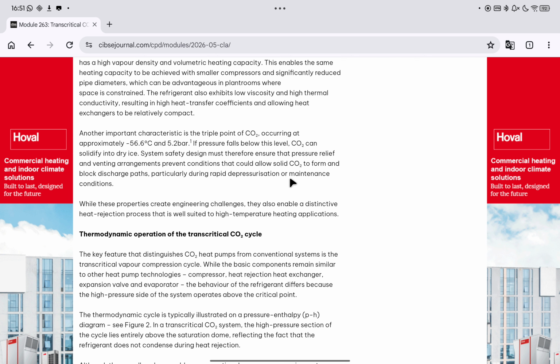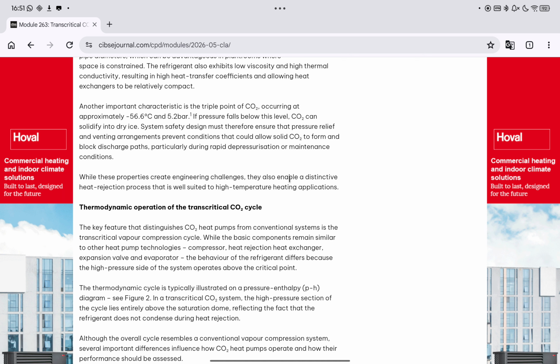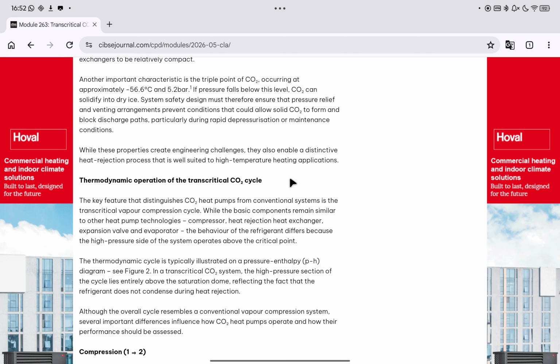Thermodynamic operation of the transcritical CO2 cycle. The key feature that distinguishes CO2 heat pumps from conventional systems is the transcritical vapor compression cycle. While the basic components remain similar to other heat pump technologies, compressor, heat rejection heat exchanger, expansion valve, and evaporator, the behavior of the refrigerant differs because the high pressure side of the system operates above the critical point. The thermodynamic cycle is typically illustrated on a pressure enthalpy (p-h) diagram.